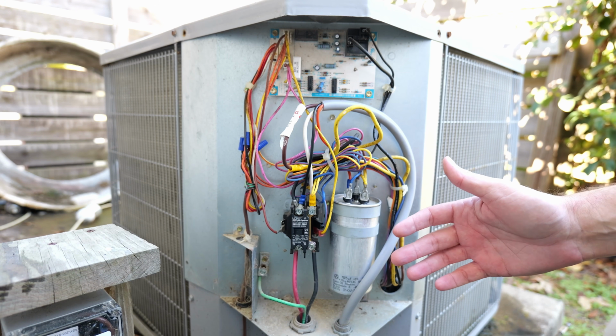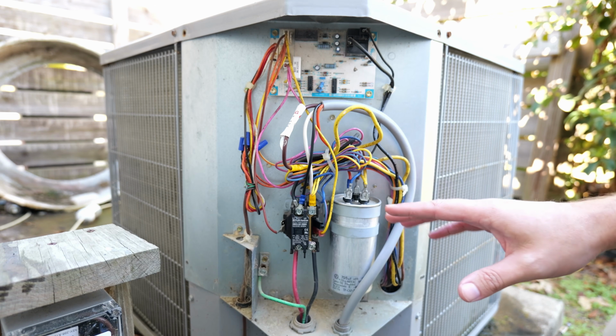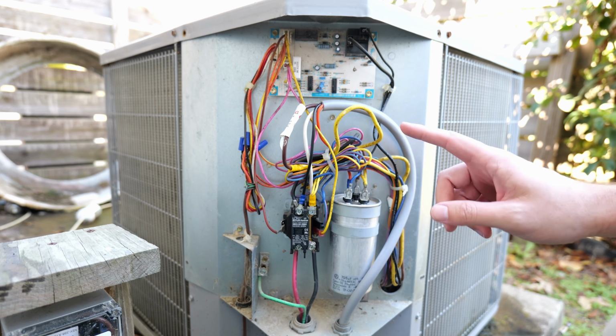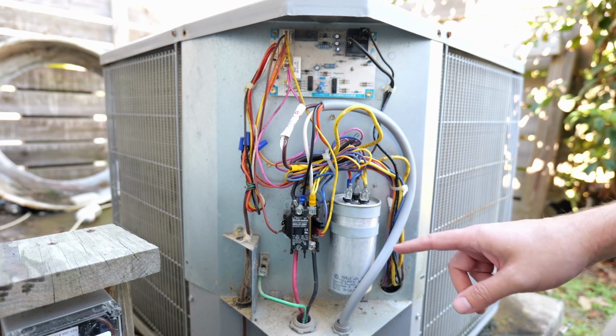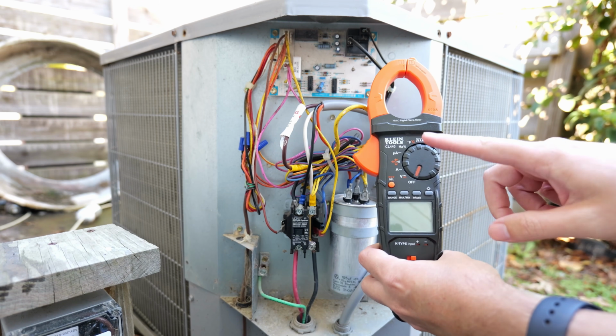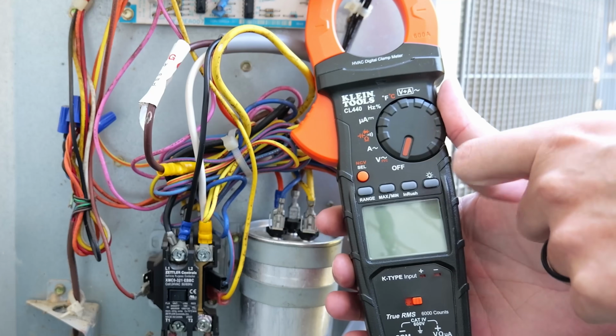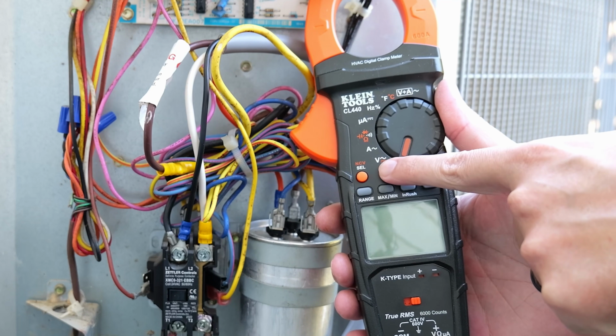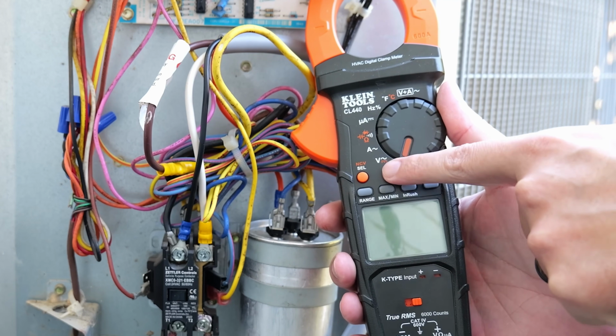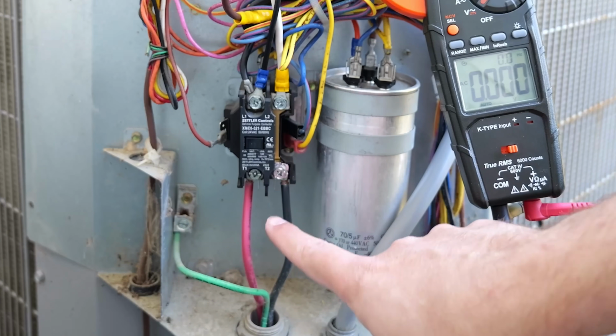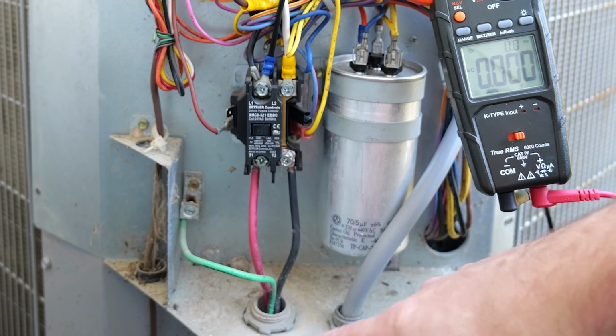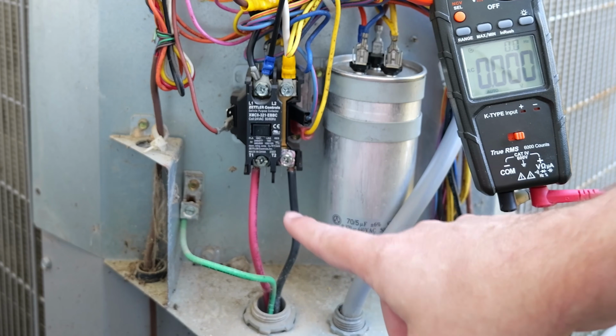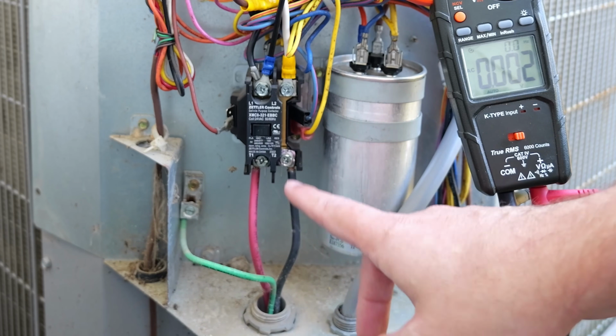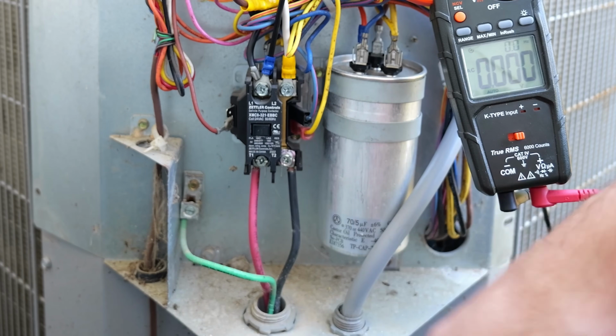But before I do anything with this, even though I have pulled the disconnect, or if you have a circuit breaker, the circuit breaker's been turned off, I want to verify there is 100% without a doubt no electricity flowing into this AC unit. So what I'm going to do is take my multimeter, turn it on to where it shows V, which is for voltage and alternating current. Now I want to check down here at the contactor where my lines are coming in at the bottom. This is where the power would be fed from, coming from the house.